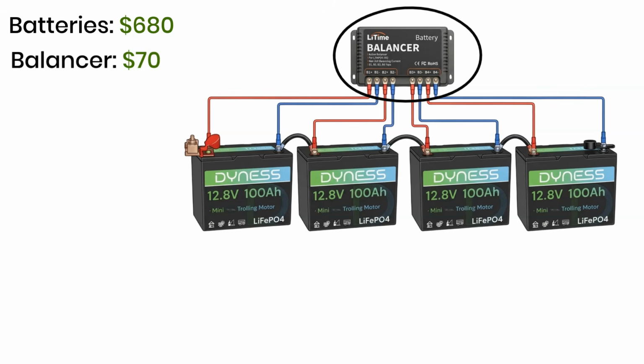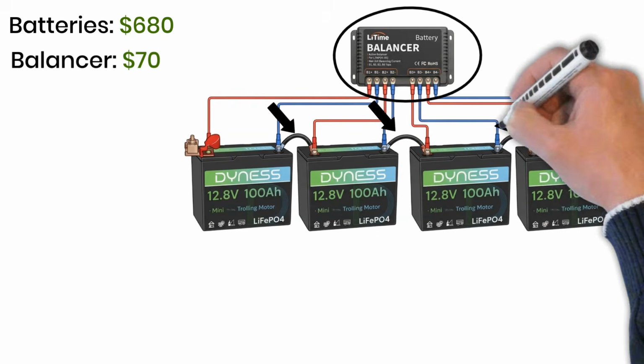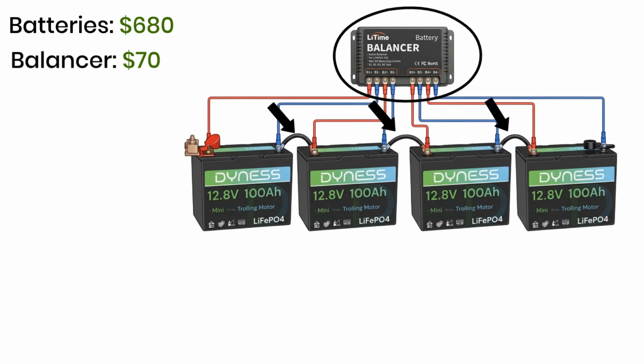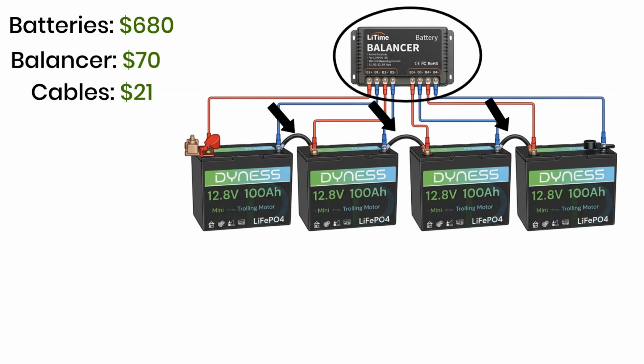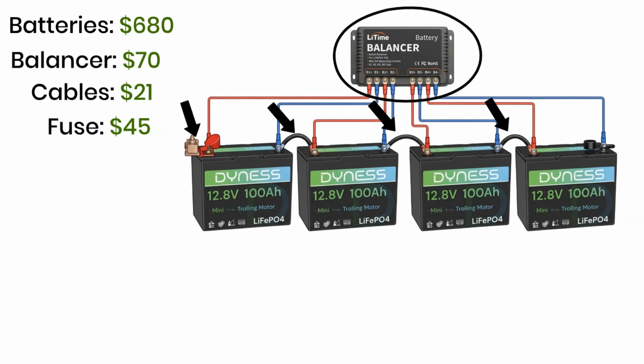Next, we need the series connection cables. To turn four separate batteries into one 48-volt battery bank, we need jumper cables between the batteries. Using properly sized cables, the cost is roughly $7 per cable, and since we need 3 connection cables, that's about $21. Then we still need overcurrent protection — a suitable fuse setup can add another $45.